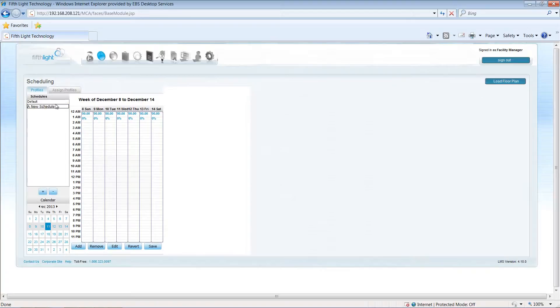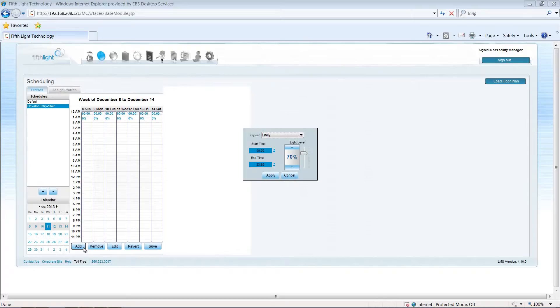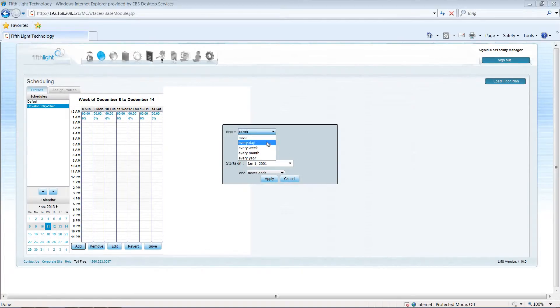Within the schedule module, I'll add a new profile and give it a descriptive name. Once the profile is created, I'll select the calendar control and choose to add a schedule. In this case, our facility wants to set the schedule to automatically run Monday through Friday, so I'll choose the option for custom recurrence, assign it to a weekly frequency, and then select the appropriate days of week.